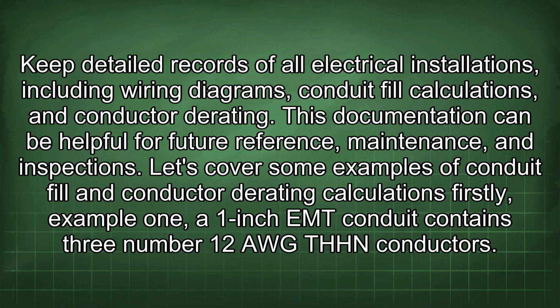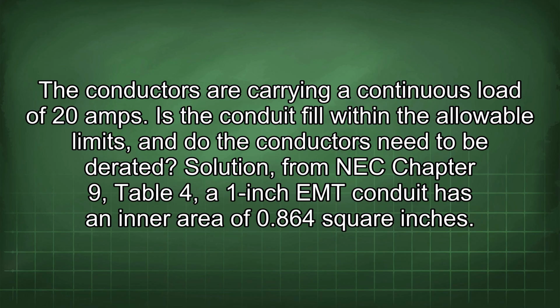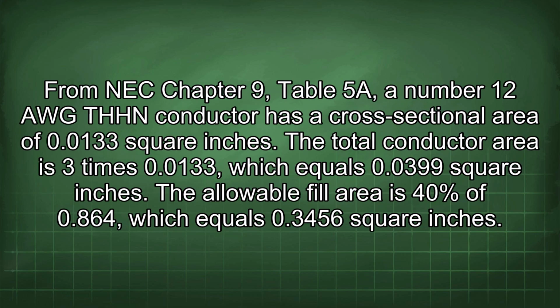Firstly, example 1. A 1-inch EMT conduit contains 3 number 12 AWG THHN conductors. The conductors are carrying a continuous load of 20 amps. Is the conduit fill within the allowable limits, and do the conductors need to be derated? Solution from NEC Chapter 9, Table 4. A 1-inch EMT conduit has an inner area of 0.864 square inches. From NEC Chapter 9, Table 5a, a number 12 AWG THHN conductor has a cross-sectional area of 0.0133 square inches.